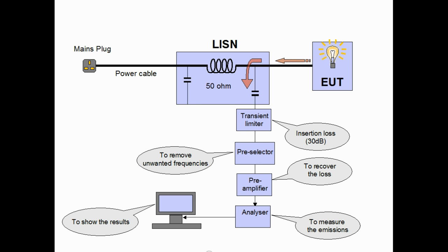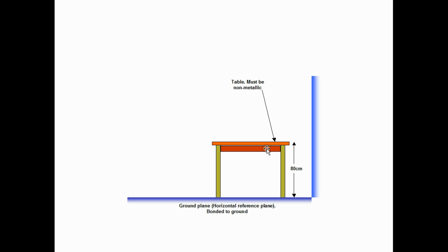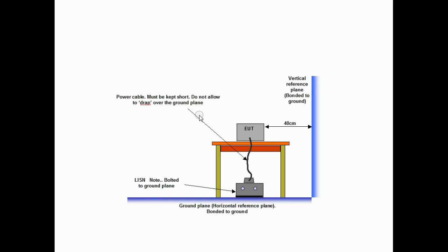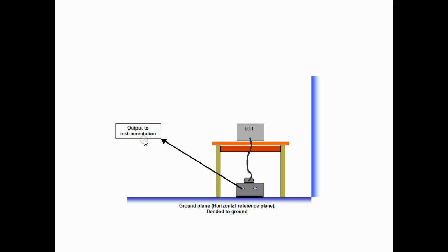So this is the setup. Now the standards define exactly how we set this up physically. They define a wooden table or at least a non-metallic table. No ground plane on top of the table but we do have a ground plane or horizontal reference plane on the floor. We bolt the LISN to this ground plane. It's bolted down to make sure we get good bonding to the ground plane and the product is put onto the table connected by a short mains cable to the LISN. The cable should be just long enough. Excessive length does not help. Finally, we take the output from the LISN to our instrumentation.